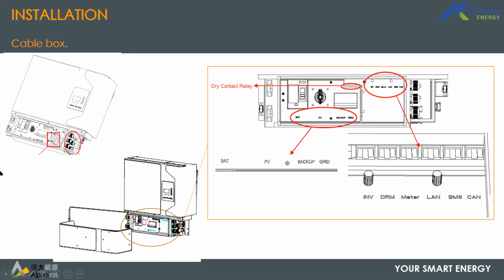And then on the right side of the picture, there is a section which is circled with inverter, DRM, meter, LAN, and BMS. So the inverter port is used when we are connecting inverters in parallel, to daisy chain your inverters. The DRM, we don't use because our battery comms is compatible with the CAN bus, with the BMS, which is built-in. The inverter, however, can take a CAN bus, but in this case, the system, as I've said, is plug and play. Everything is pre-programmed.